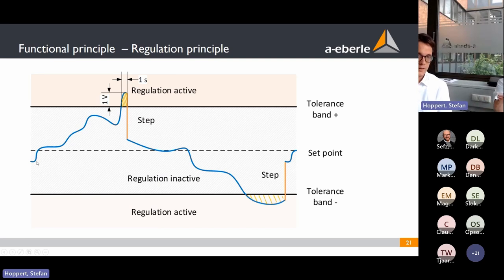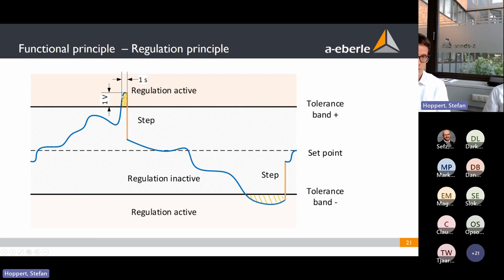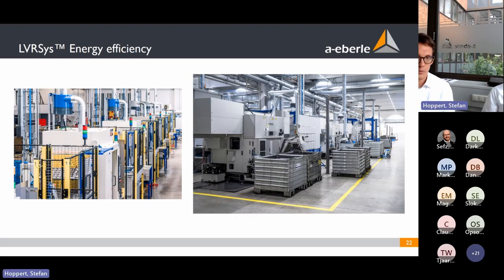The regulation principle: the blue line shows the fluctuating voltage. When it goes above the tolerance band, the system steps down; when it goes below, it steps up. The regulation speed — how long it takes per step — is a configurable parameter, set at 1 volt per second by default. Standard parameters work well for most applications without any additional configuration.